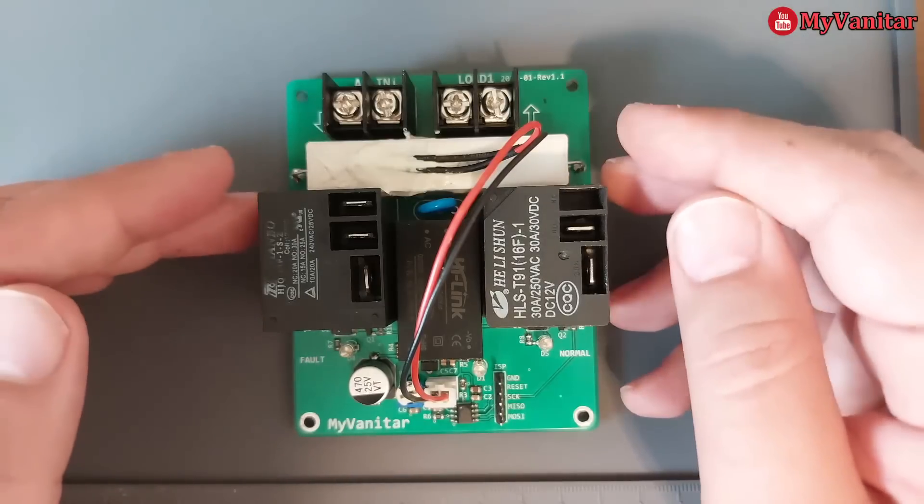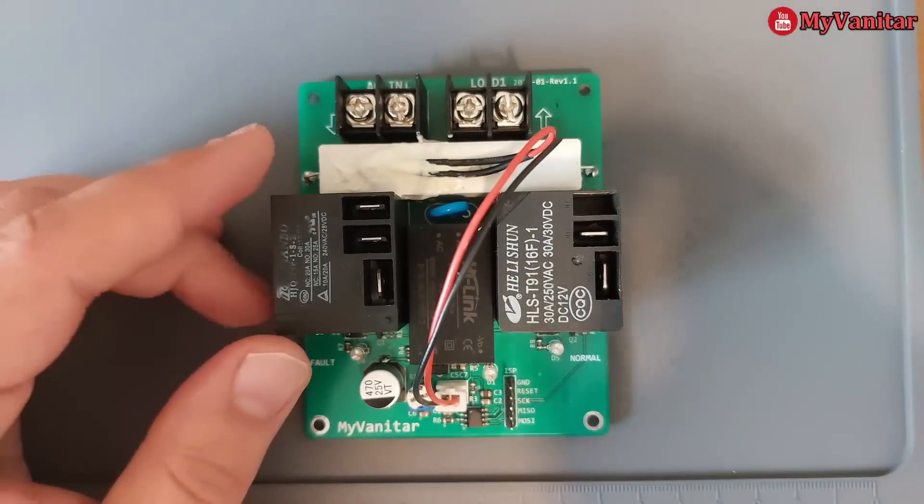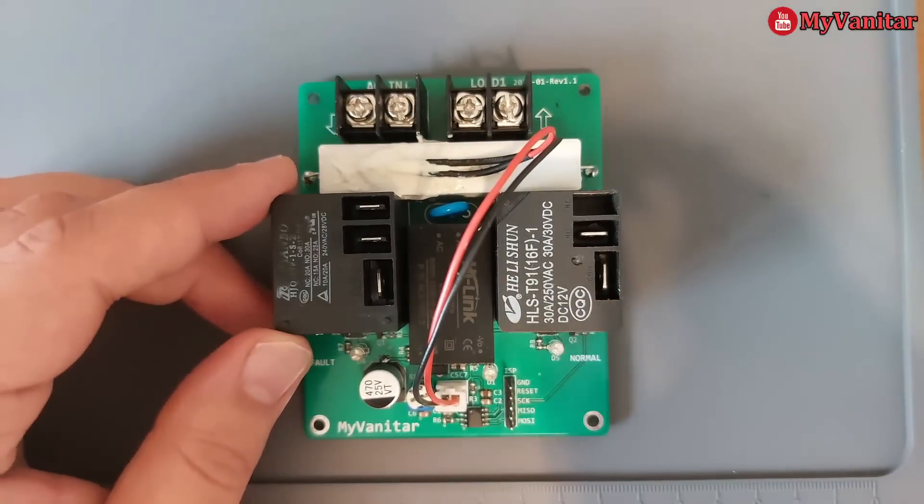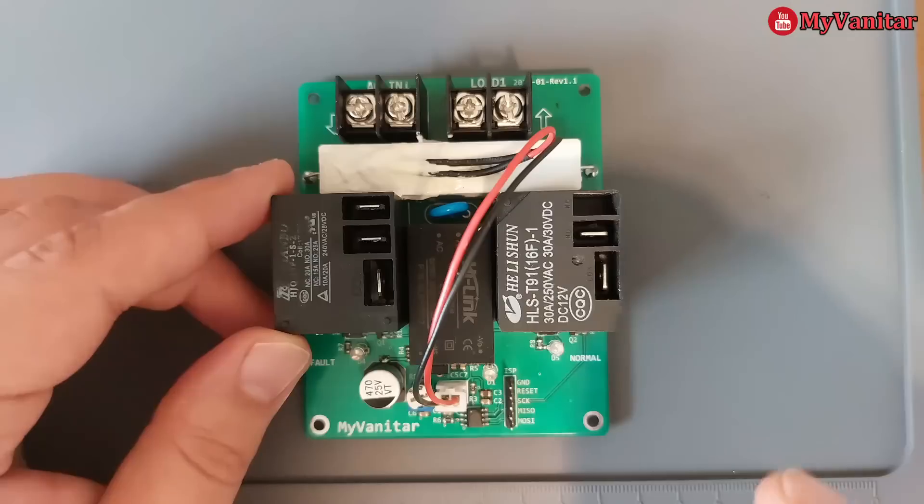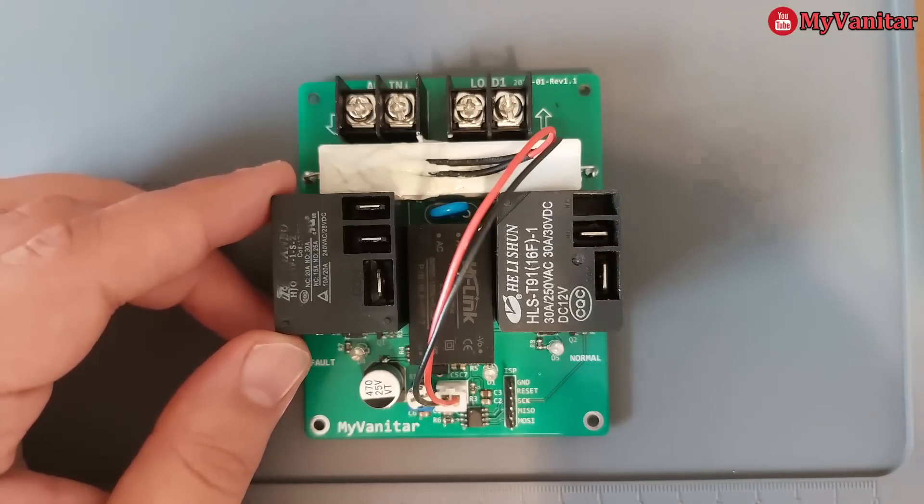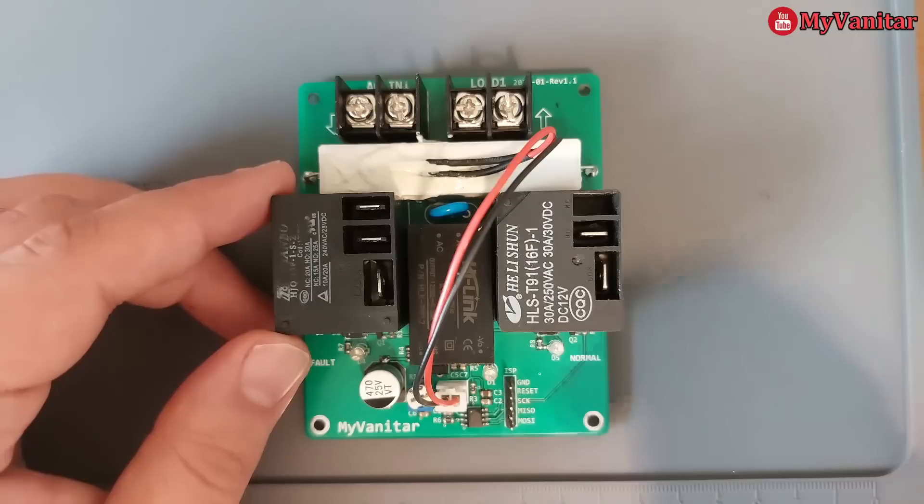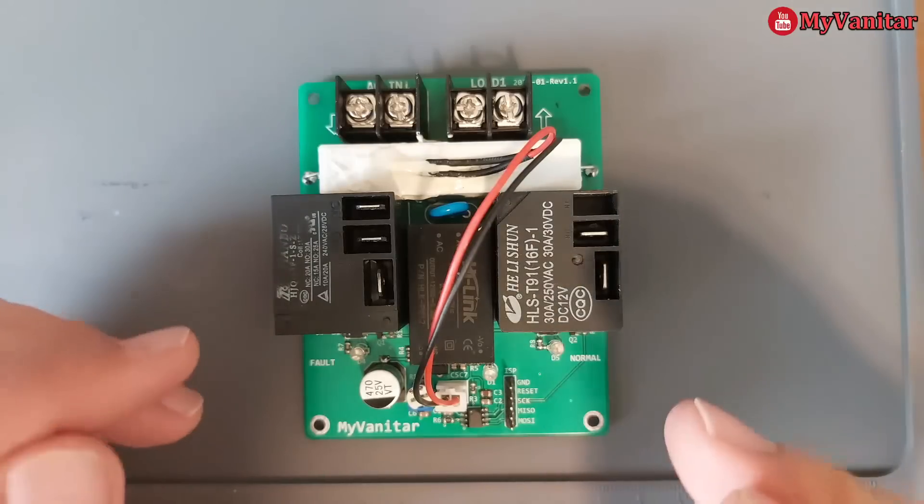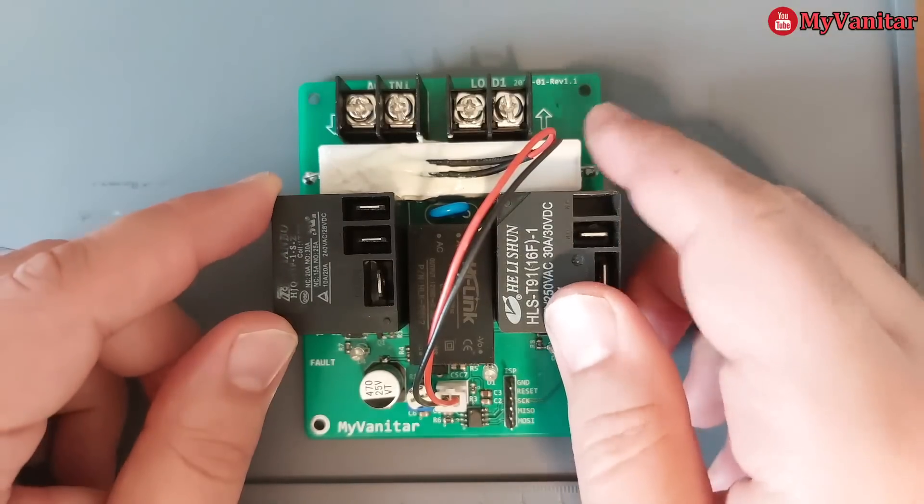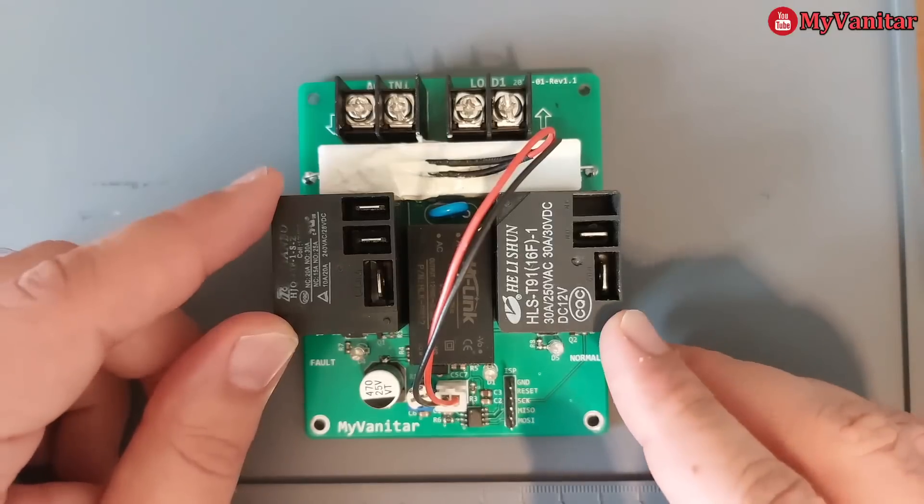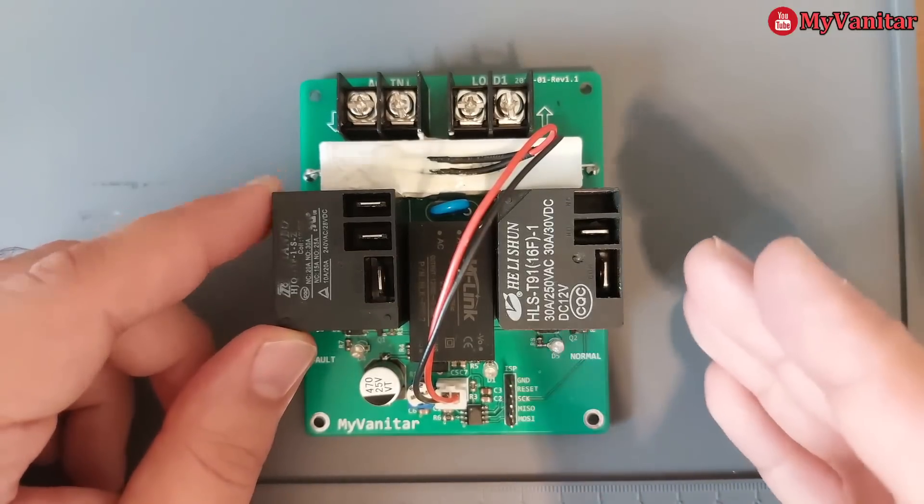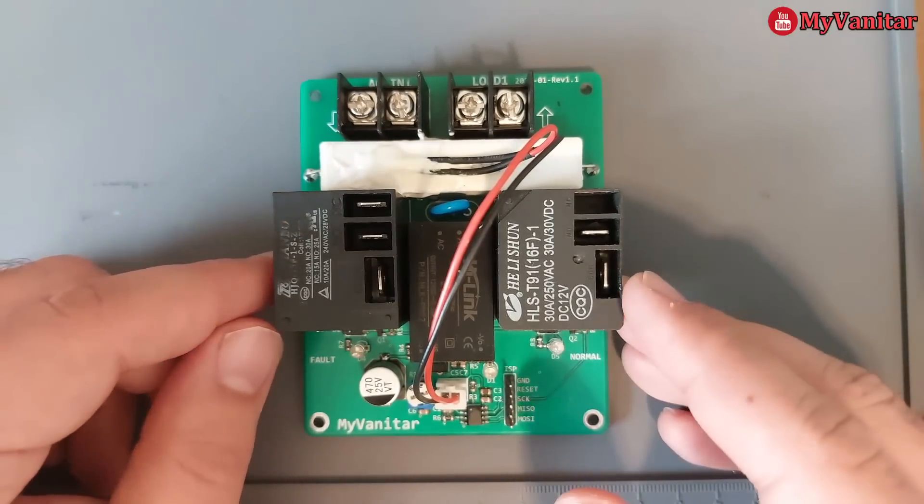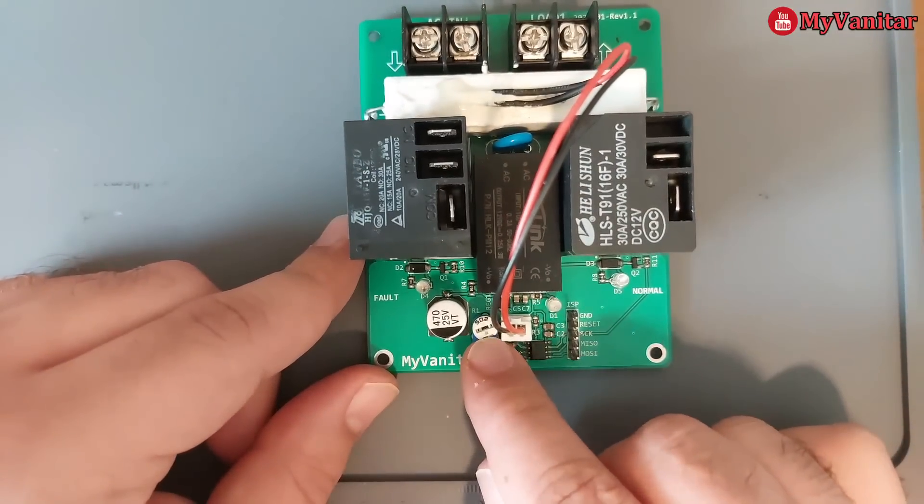The relay shorts the power resistor and applies the full power to the load. At the first time when you connect the load to the power, that's when the load needs a huge amount of current. That current should be limited using this resistor. After that delay, the full power should be applied to the load.